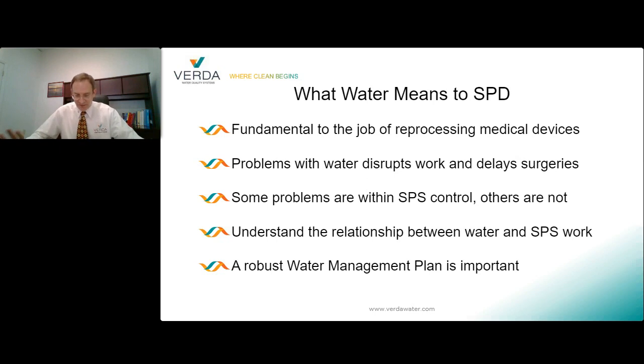So first, some background. There are many ways water is used in the SPD. It's used in soaking, washing, rinsing at sinks and washer disinfectors. It's the agitating fluid in ultrasonic cleaners. Water is used in several processes in sterilizers: it helps generate the steam, it generates vacuum in some cases, it can cool vacuum pumps, and the water can be used for blowdowns if the sterilizers have integrated steam generators.